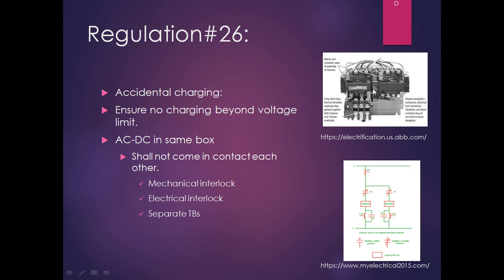One is a mechanical interlock. You can see there are two contactors and there are two levers. This is the lever for one contactor, this is the lever for another contactor. If one contactor is pressed, the lever is pressed. At that time, if somebody or electrically the second contactor wants to be pressed, this lever will prevent it from pressing. That means only one contactor will be on and the other contactor will be in off condition. This is the mechanical interlock. This is a bit rare, but electrical interlock is very common, and even though mechanical interlock is present, electrical interlock is usually provided as a backup, and sometimes electrical interlock is provided standalone.